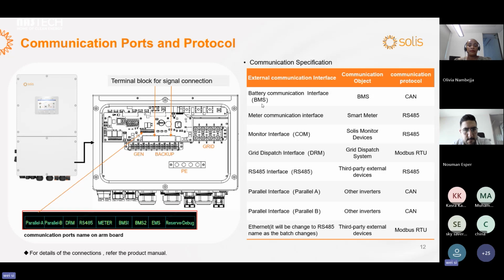You can see the communication protocols we use for the different devices. For the battery, we use the CAN communication protocol. For the meter communication, the monitor interface, and almost all other devices and third-party external devices, we use the Modbus RTU communication protocol. For the parallel function, we use the CAN protocol. In the old version, we had the Ethernet port, but it only supports Modbus RTU, so we will change this name to RS485.